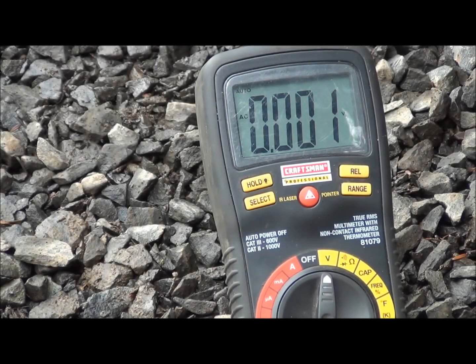Okay, I've spent a few minutes reading the technical manual, and I've determined that the overvoltage trip set point is 153 volts plus or minus 3 volts. Now, what I've done is hooked up my voltmeter across the output of the generator, and what I'm going to do is start up the generator and verify that the output agrees with the generator's built-in voltmeter. Now, what may be going on is that the voltmeter is reading too low of a voltage, and I may just have the output set too high, and the overvoltage trip may be functioning just the way it's supposed to. I'm also going to verify the frequency meters, and I'll be doing this check across all 3 lines on the output of the generator. So let's go ahead and get the test started.